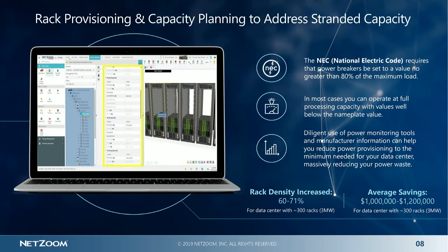PDUs, UPSs, and power breakers are only allowed so much power draw, and since a power source can only support so much, we end up with fewer devices on the rack to avoid hitting that threshold. This leads to racks only being allowed so many devices, especially if those devices have high nameplate power values.